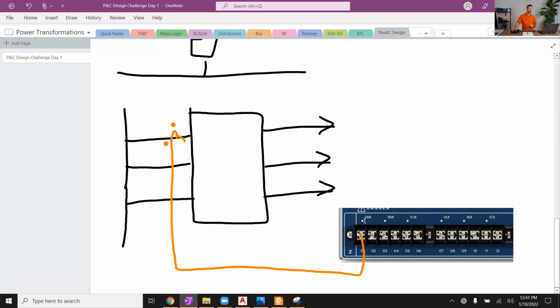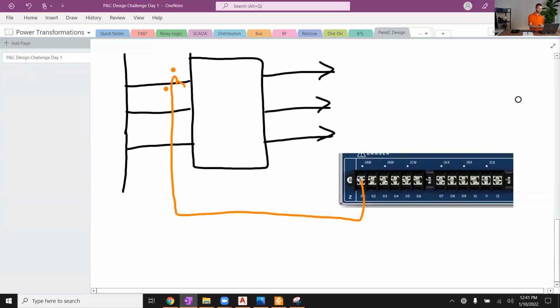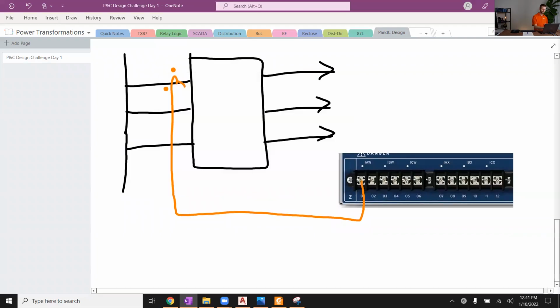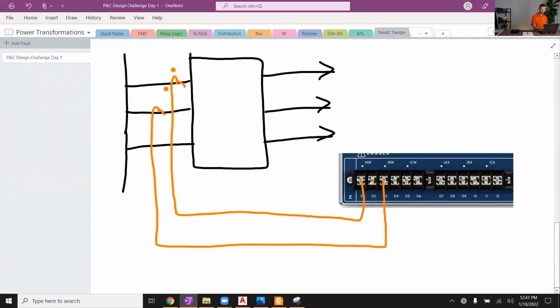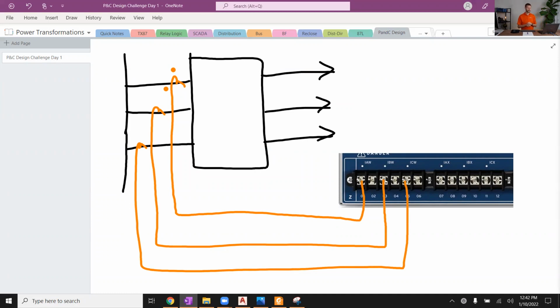And that's going to give you proper orientation so that current into your line zone of protection equals current into your line relay in the positive direction here. And you would see the same thing when we go to CT number 2 and 3: B phase will come here, C phase will come here to that polarity dot.